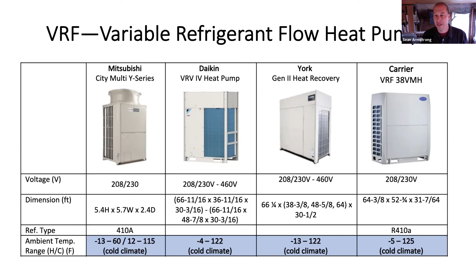As an example, this was $23,000 per apartment in Maryland with VRF, whereas ductless mini splits were $13,000 per apartment. The savings were so significant that they built a balcony on every apartment, about $6,000 each, to put the compressor there. Everyone got a balcony, and they still saved another $5,000 to $6,000 per apartment compared to VRF. So you don't do these unless you kind of have to, because they're wicked expensive.